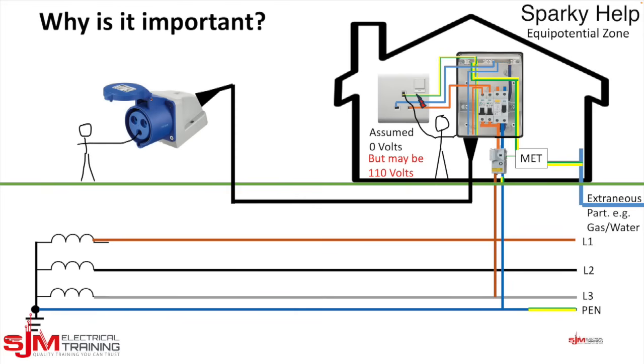Now what happens is someone could touch the exposed conductive part. You get the idea that they touch the CPC from that building. This CPC, because it has come from another building that has a fault in it, is at 110 volts. So they're touching something that's at 110. Because they're not in the equipotential zone anymore, they're standing on the ground, and the ground could well be at a different potential.